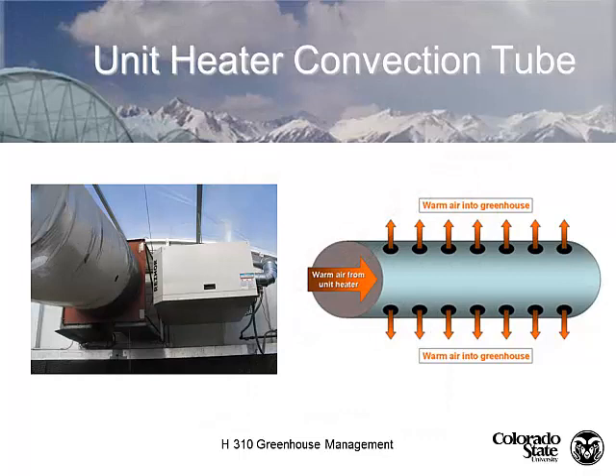Here's another jet tube system where the unit heater connects directly, goes into a baffle, and is pushed out through the jet tube. It works pretty efficiently, but does cause some shading. Is the tube retractable? No, it's hung up permanently. Most people run a fan 24-7 just to keep it open and keep air moving. We're finding it's more efficient now to use HAF fans rather than these.